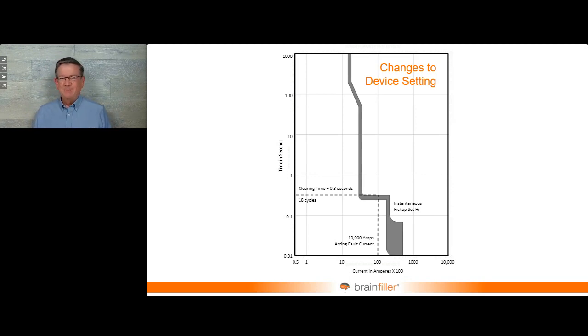Yeah, anybody that's been around the block a time or two knows that when a device trips, some people are kind of inclined to boost the settings. Don't do that. Find out why it tripped. Talk to somebody before you adjust the settings, because that can have a big impact on things.